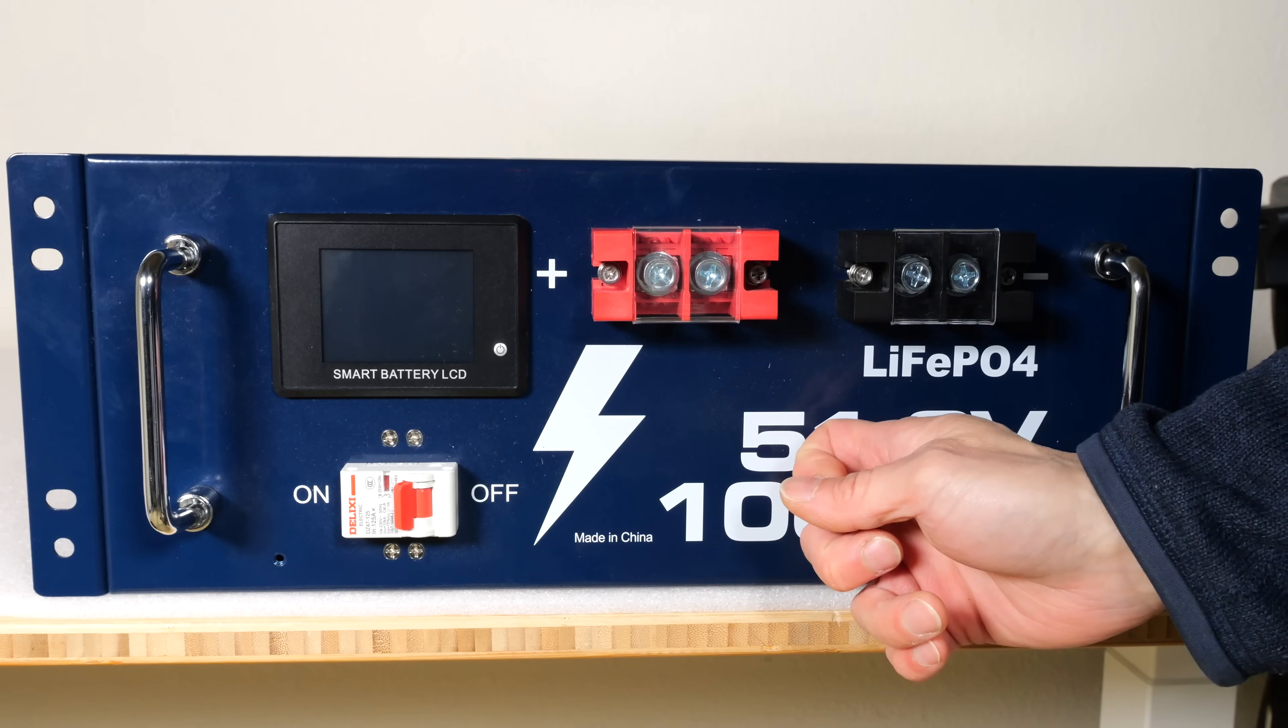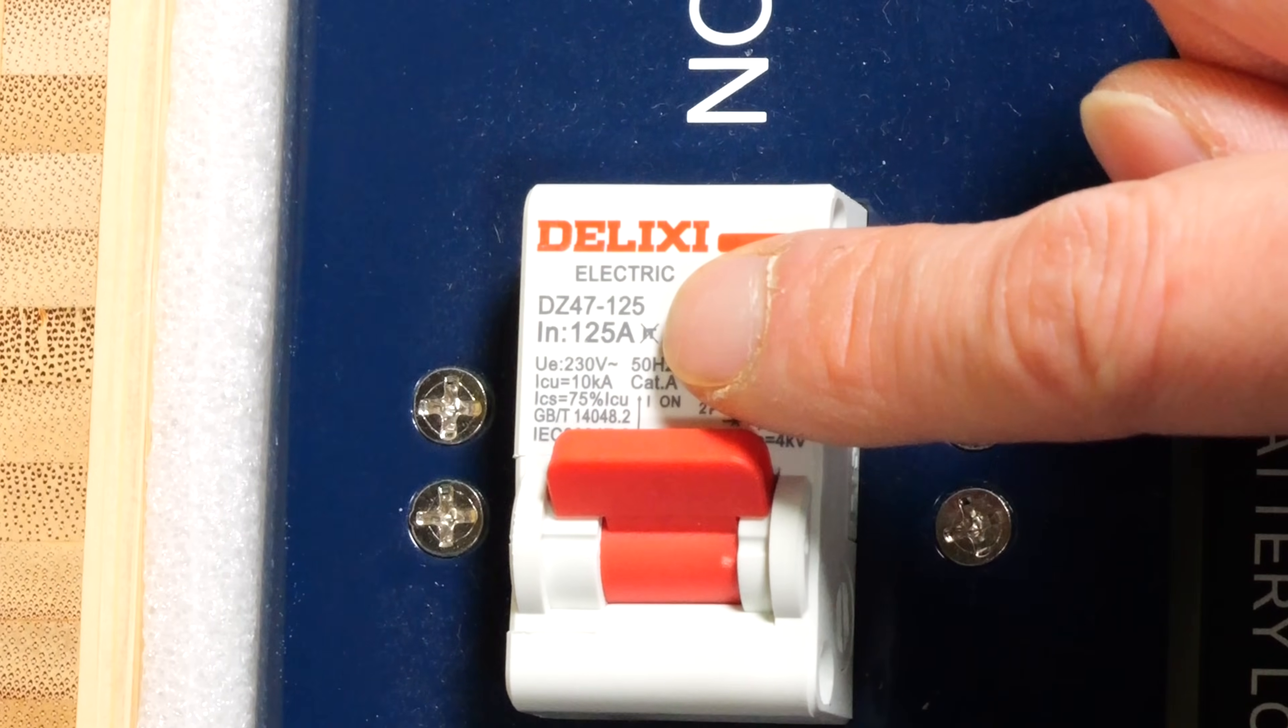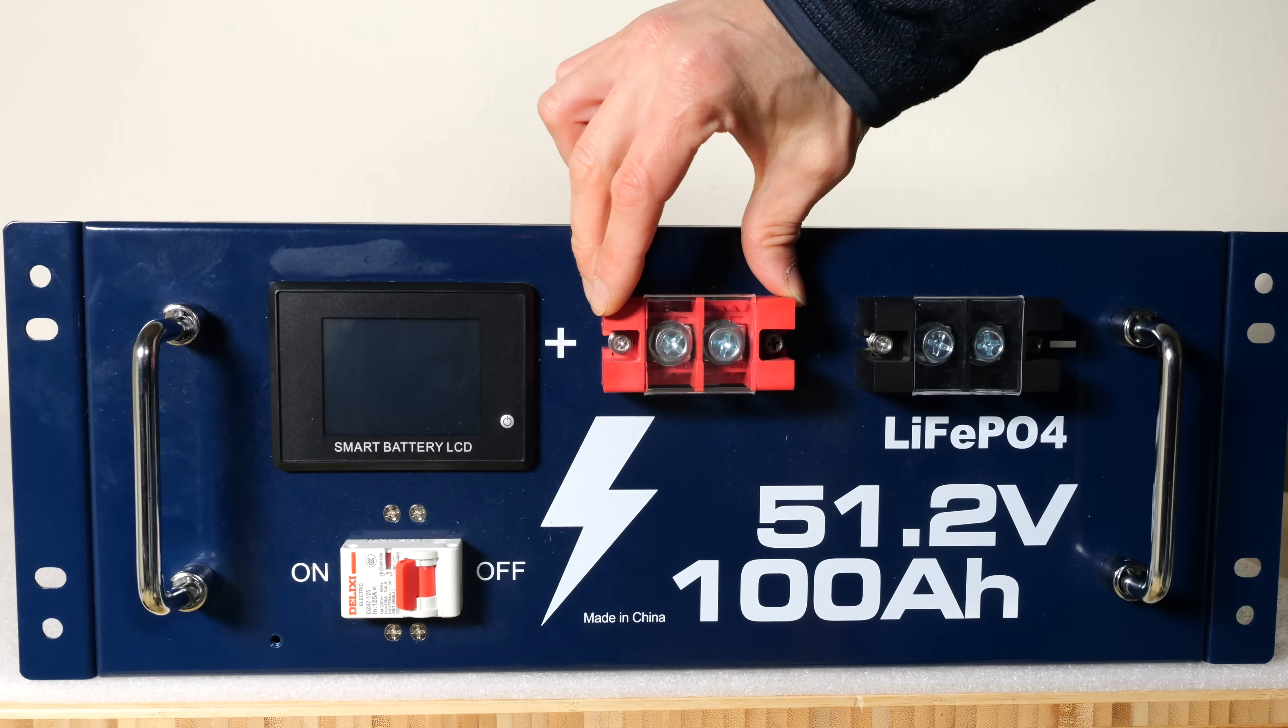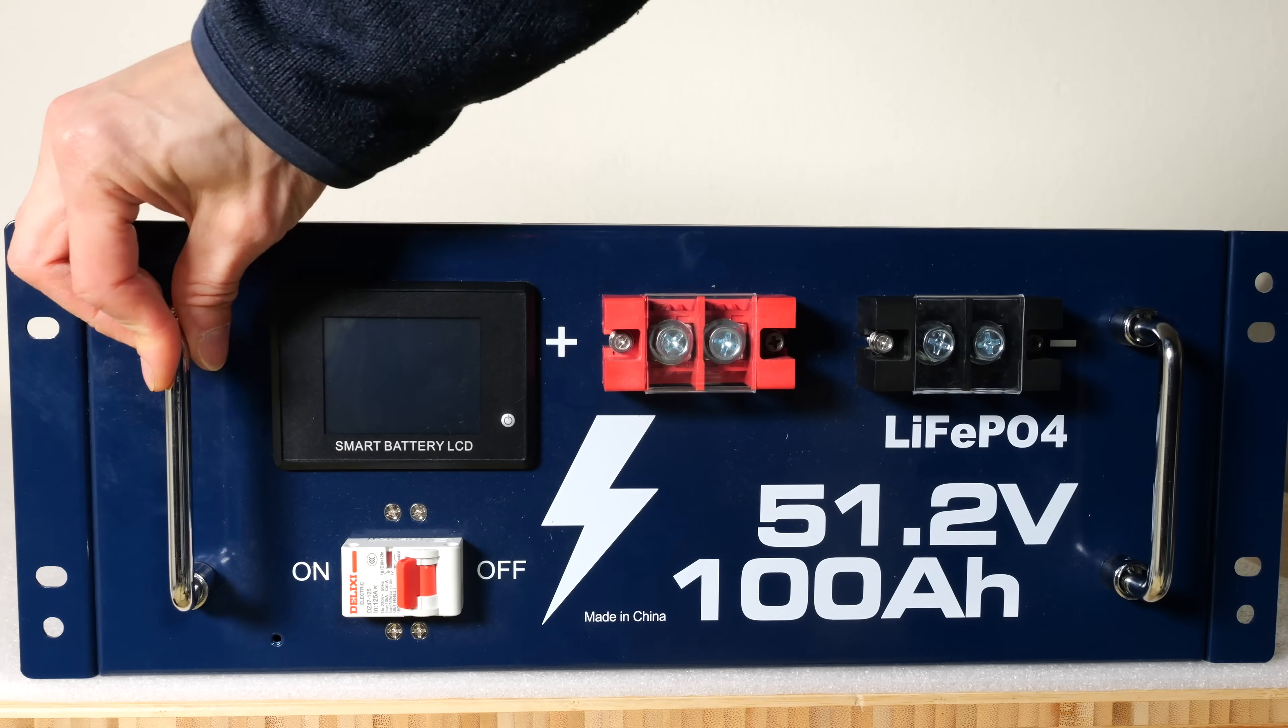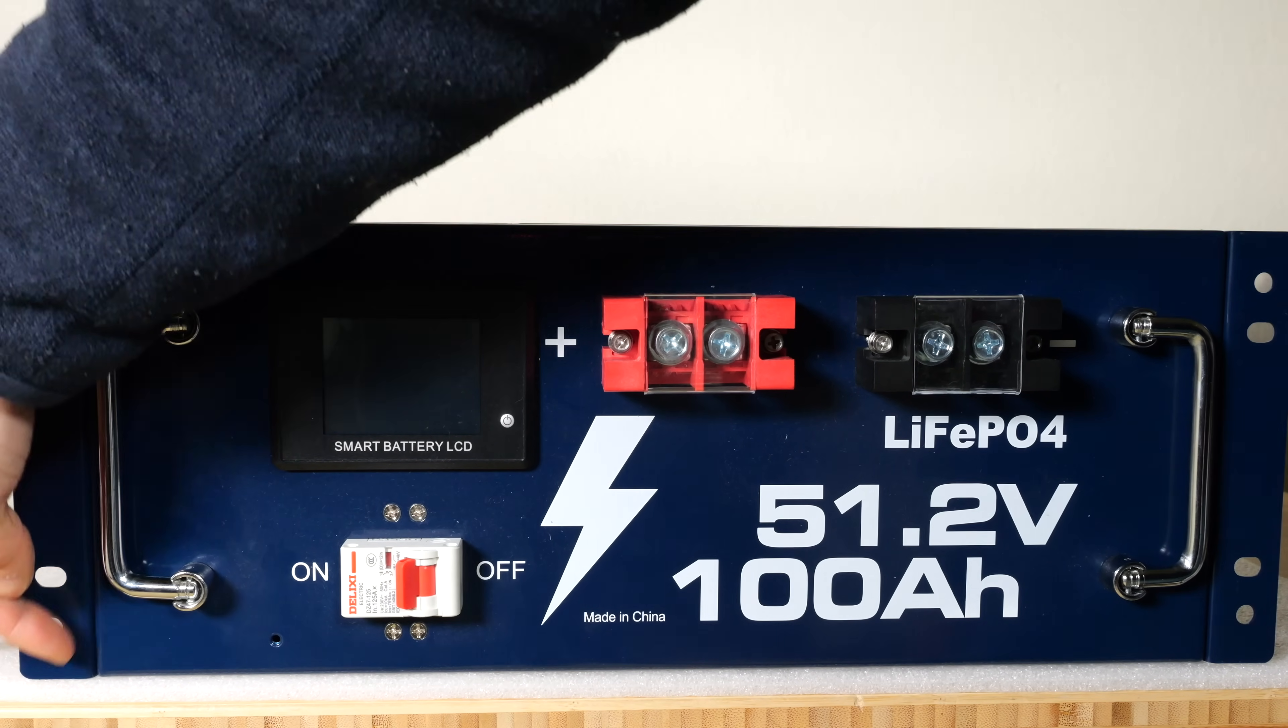You got two screw positions, so you can daisy chain them. You can parallel a couple of these together. It has a built-in fuse. This one is the Delixi Electric 125A fuse. If you disconnect this, it will be disconnected from these terminals here. The front handles are swivlable. It doesn't go this way, only outwards. And then on the side, you have the rack mount holes.